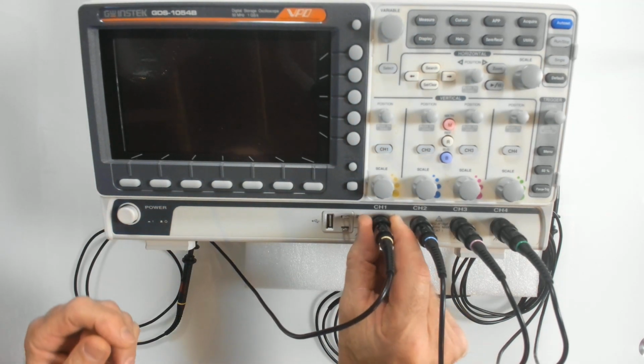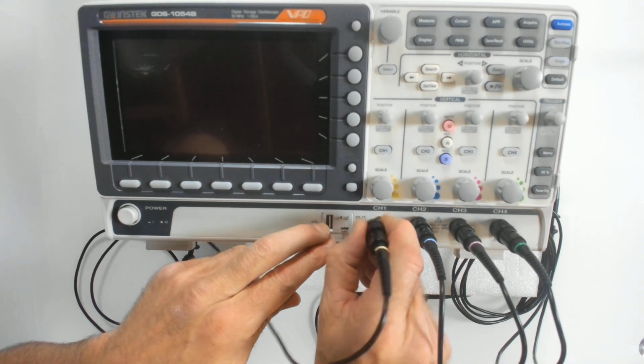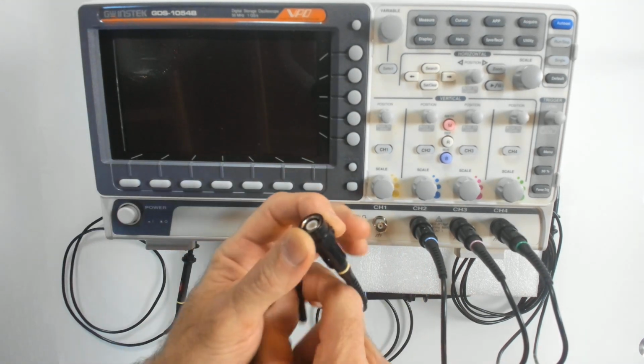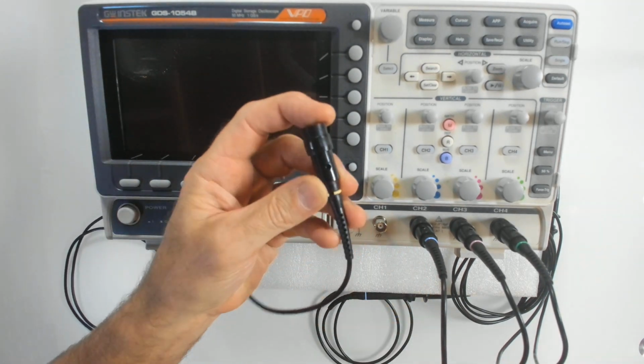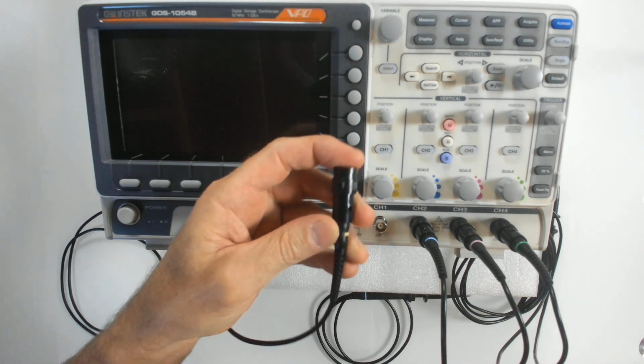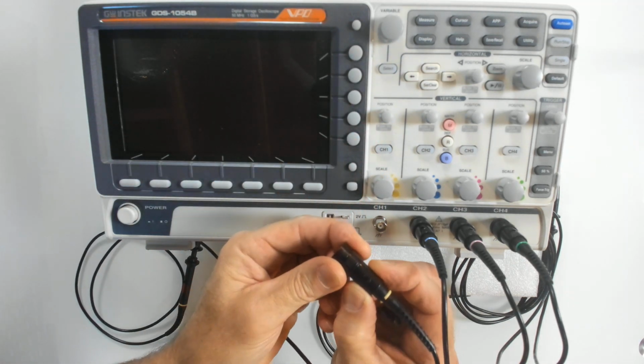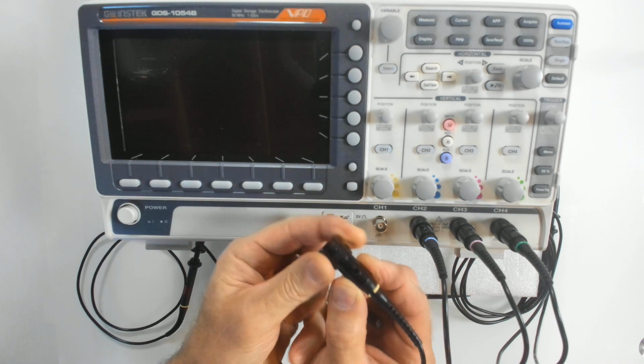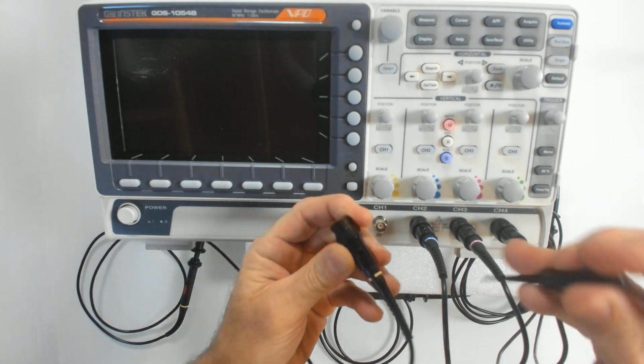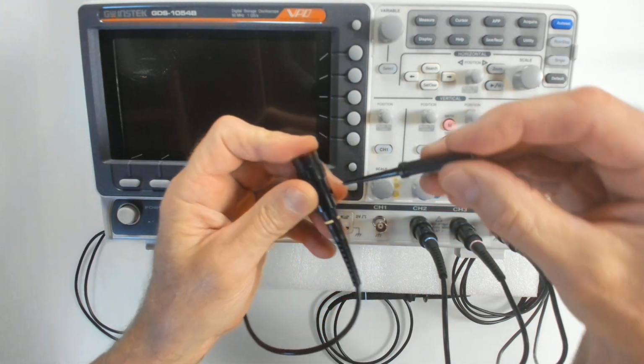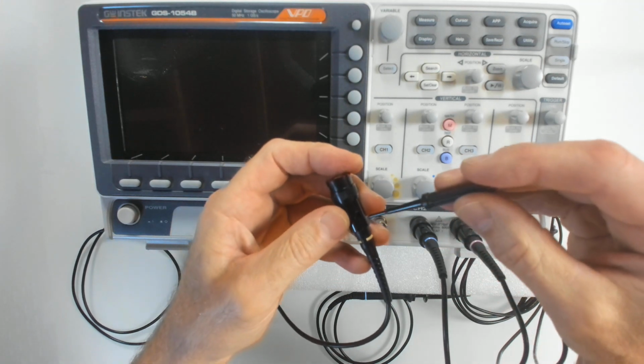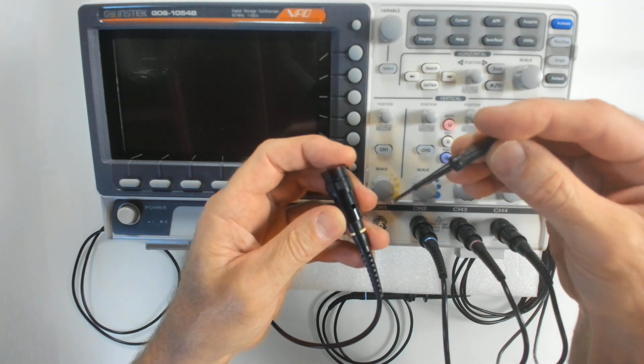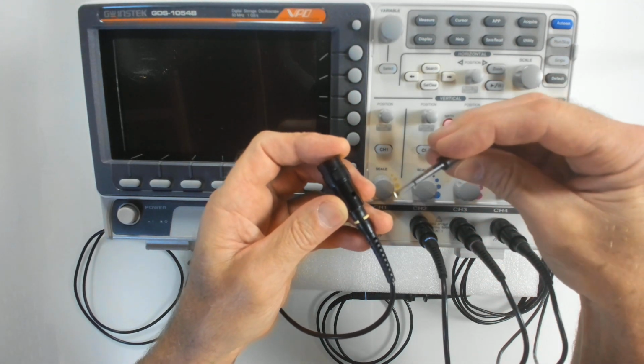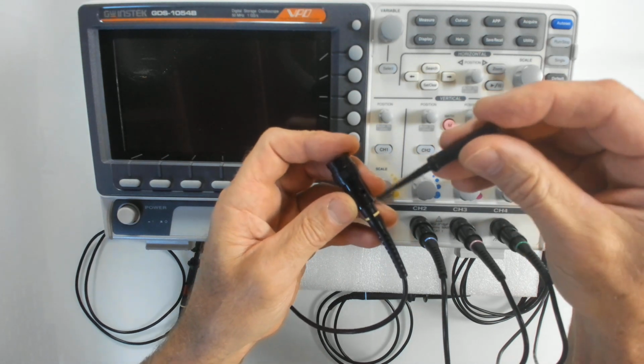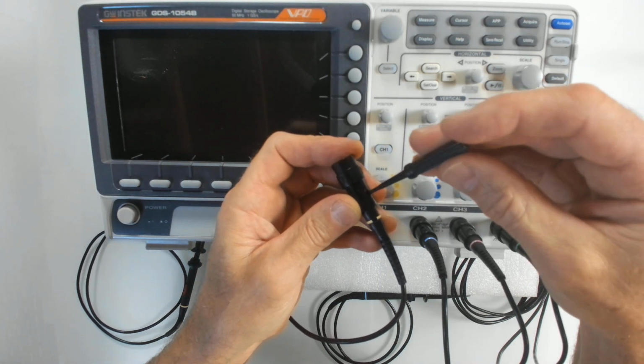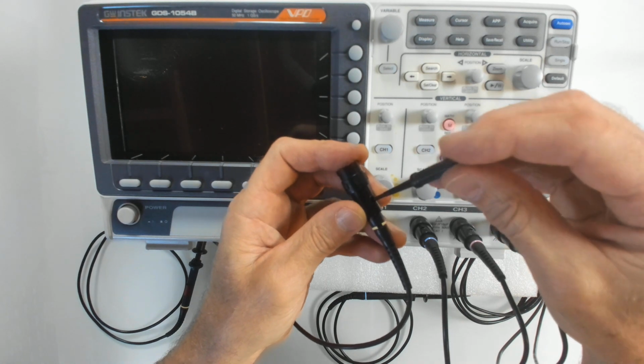Also on this end of the probe, there's a little adjustment screw that we'll be using in a few minutes. And so what you need is this barrel here can rotate it to a position where you can have access to that with a little screwdriver that's provided. Don't just use this one. This one's intended to fit, and you want to very carefully, without too much pressure, find where that slot lines up.